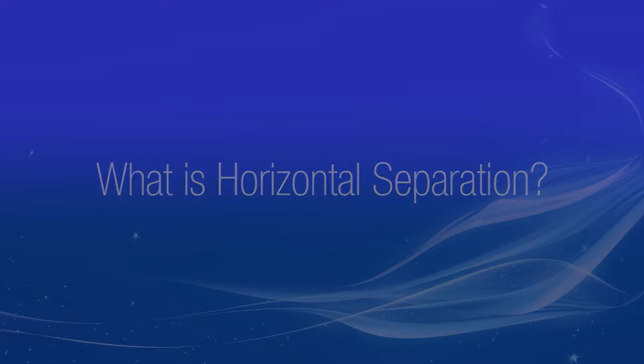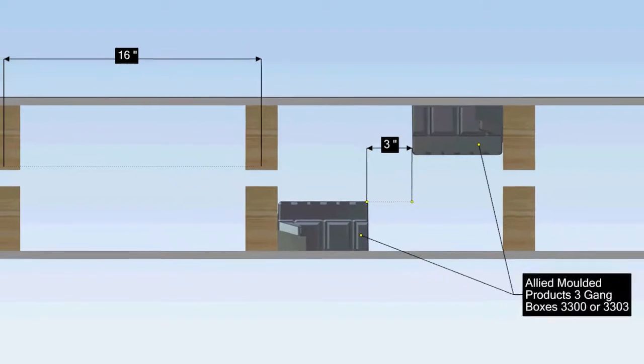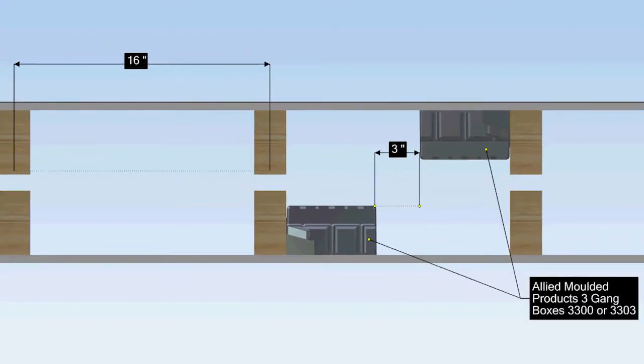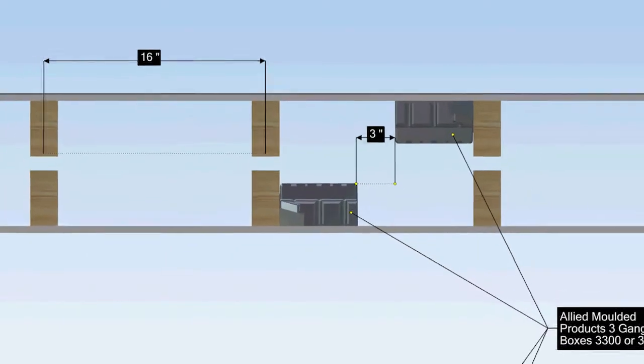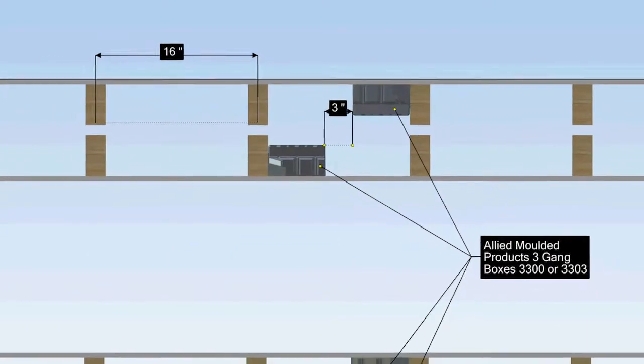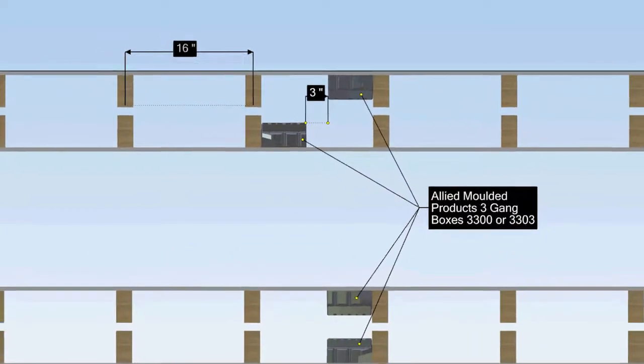Three-inch horizontal separation is achieved when two of our fiberglass boxes are placed horizontally from each other in the same stud cavity. Horizontal separation refers to the location of electrical boxes in a horizontal plane facing adjacent rooms or apartments.